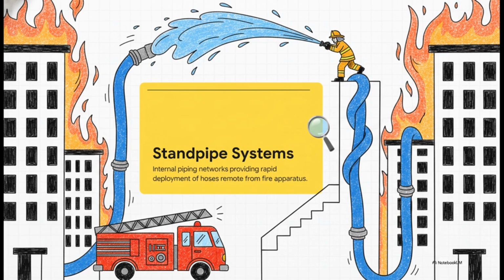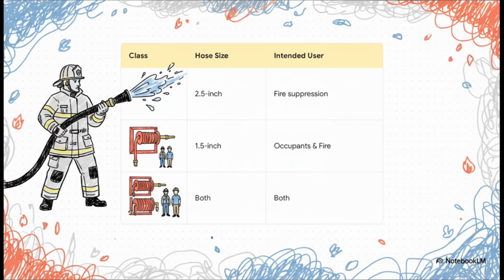It is entirely about expediency and saving vital, life-saving minutes. Now, these standpipes come in 3 specific classes, and it all boils down to who is actually intended to use them. A Class 1 standpipe provides massive 2.5-inch hose connections. These are strictly for trained fire suppression personnel who are handling large, high-pressure hose lines.